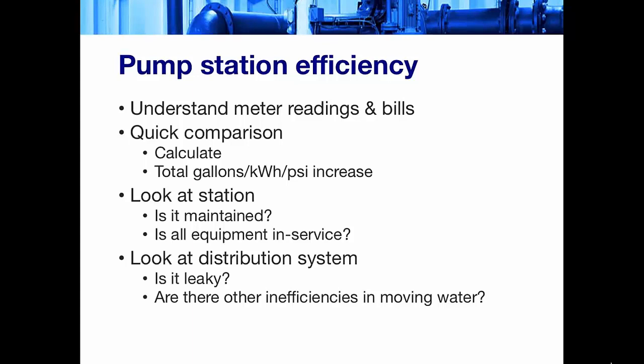First, going back to Dawn's point, understanding your meter readings and the bills that are tied to each pump station is important. If you don't have the actual energy use at the facility of concern, you need to get that prior to beginning to judge the efficiency. So you can do some quick calculations, and a relatively simple calculation would be to total up the total gallons pumped within a month, and hopefully your pump station units all have individual meters that you'd be able to do that. You would also need to have your kilowatt hours for that same month. And then to make things equal to each other, you would need to also include the amount of pressure increase within your calculations.